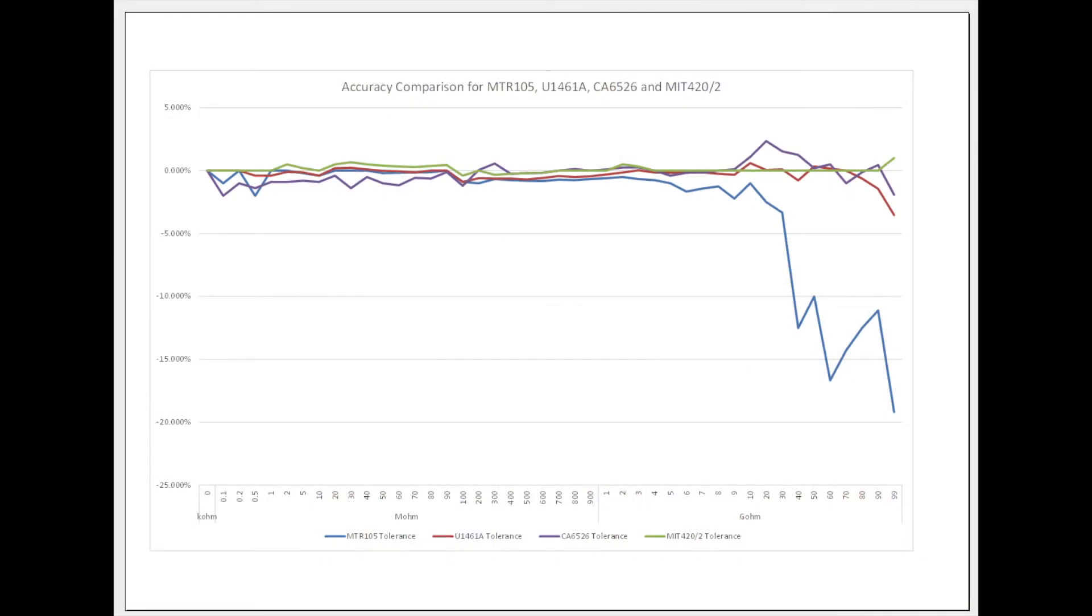So the other plot I have here is for a comparison to other instruments. This is actually the MTR105, the Keysight unit, a Chauvin Arnoux unit and the Mega MIT 420 that I have. You can see all these other units follow a fairly straight line graph across. You can see the 1461 drops away a little bit at the 99 gig ohm test but the MTR105, you know 20 gig ohms, you see it's starting to drop away from the rest of the instruments there. But interestingly the 420-2 does seem to be accurate, it's just this MTR105.